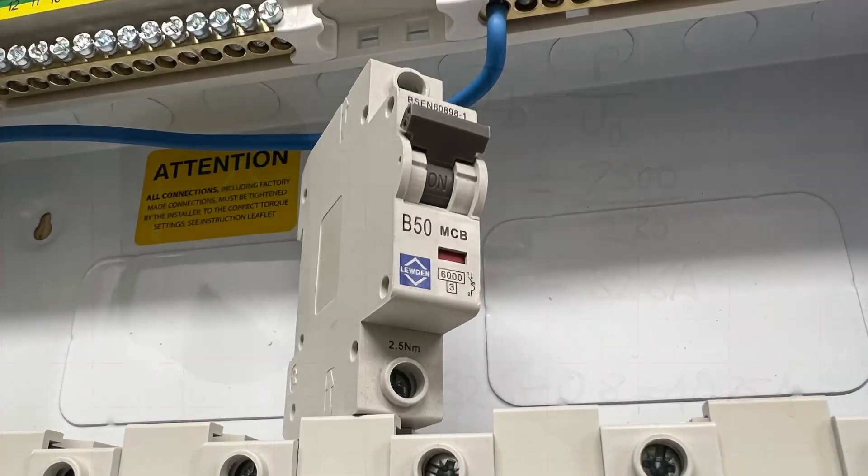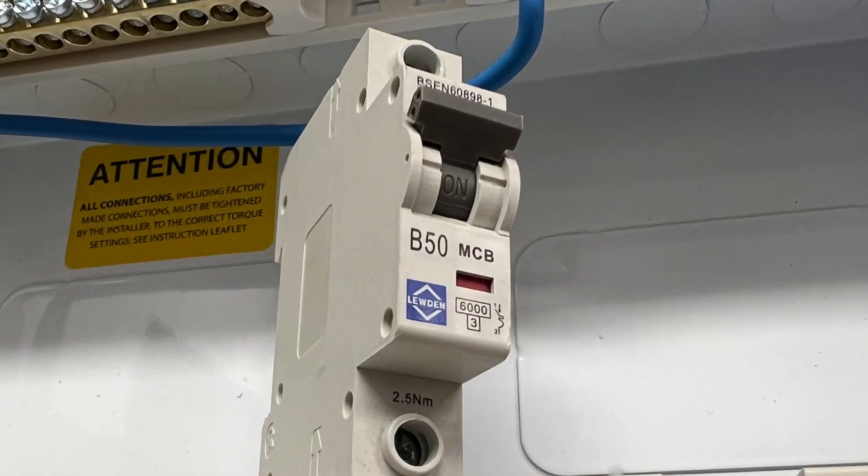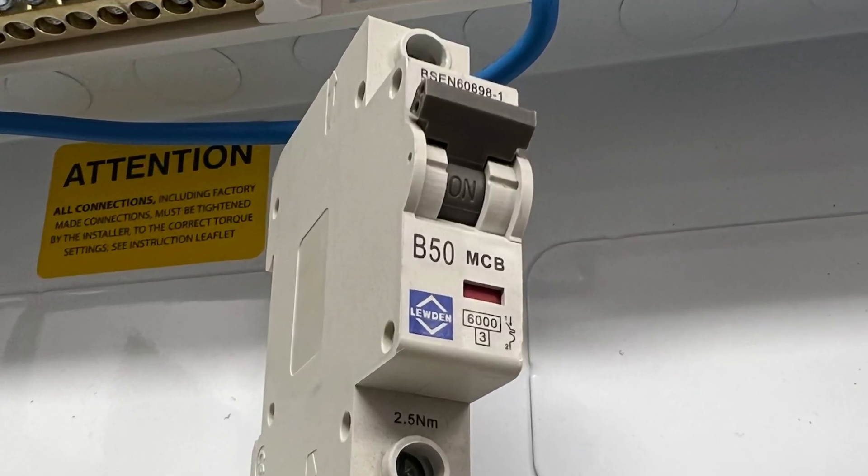That 40.75 amps is the value we'd use to select our protective device. So the next breaker size up from Lewden is 50 amps, and if we want to provide overload protection to the circuit, we'd use that 50 amp rating to size the cable. You can see that this rated diversity factor can materially impact on the circuit design and may end up needing a larger cable size installing.